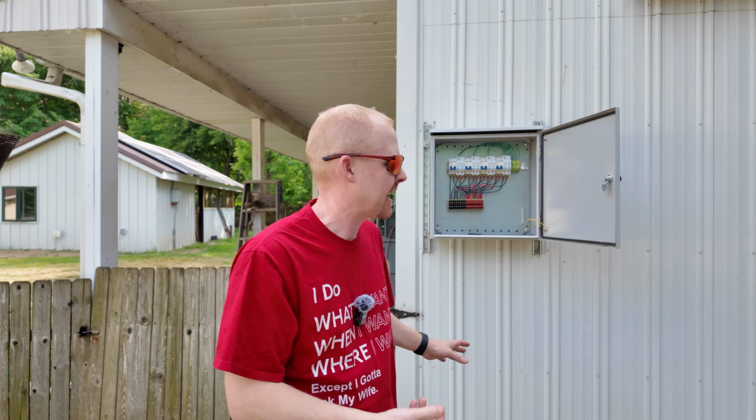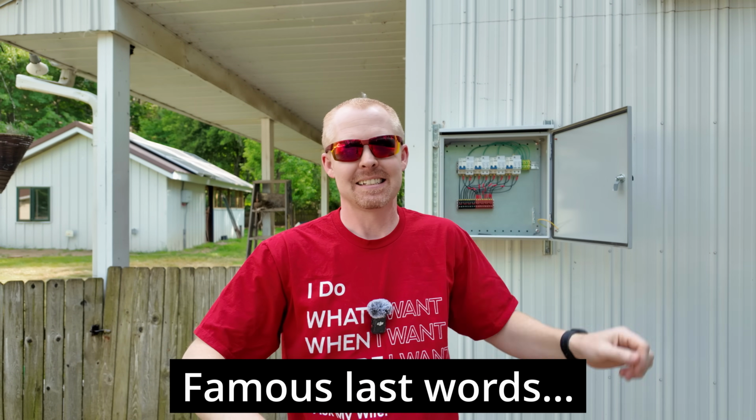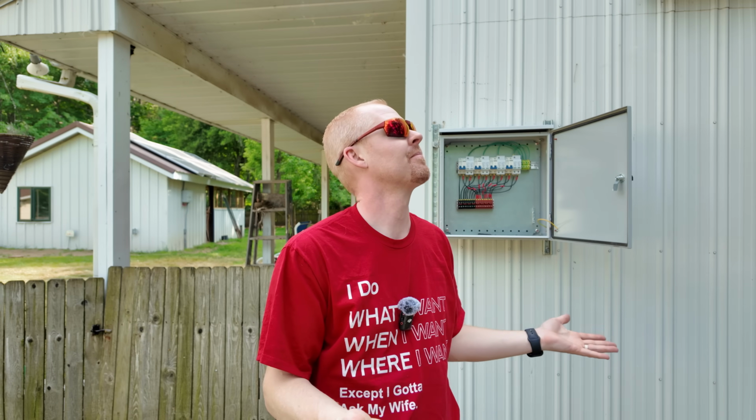So hopefully figuring out all this was really the hard part. So I'm going to start working on cutting the conduit and running the conduit for the new lines. And hopefully there'll still be some daylight by the time I get done. It's about 5:30 right now in the evening. And I did let the batteries charge up fully all day long, which was really a good feeling, because then I can take the PV offline for the rest of the evening while I'm working on running these lines.